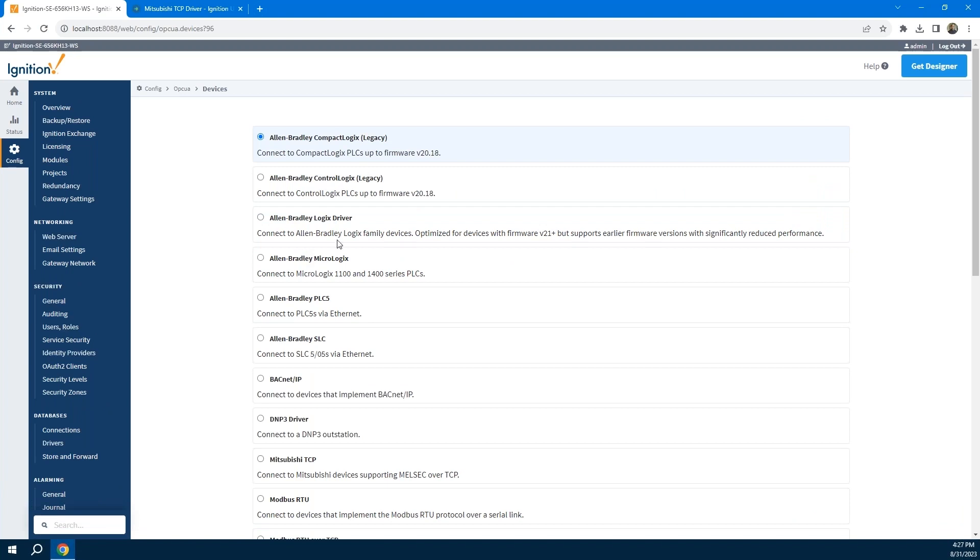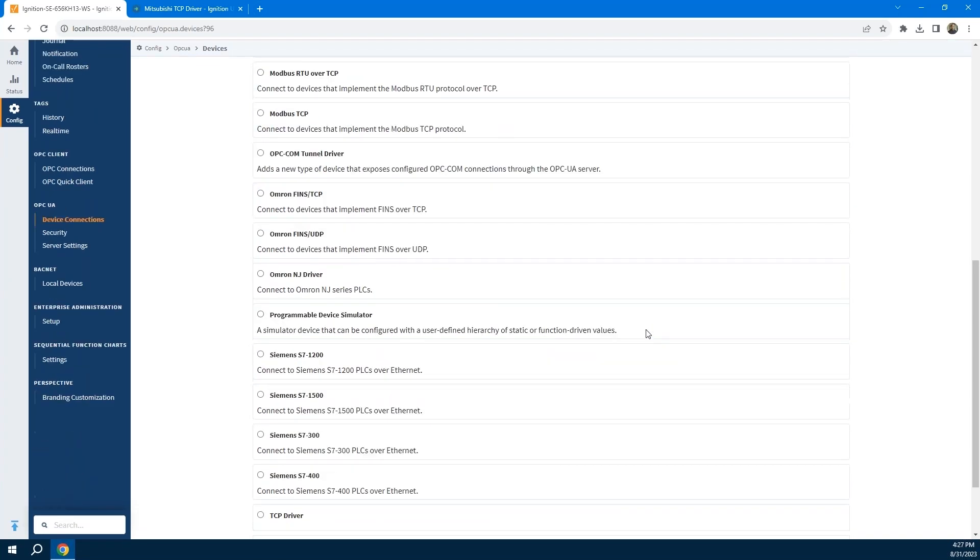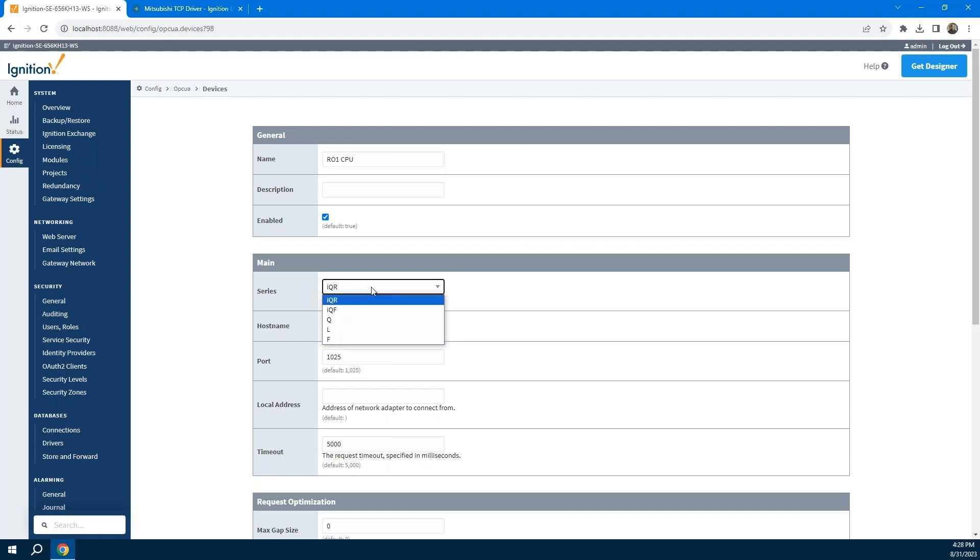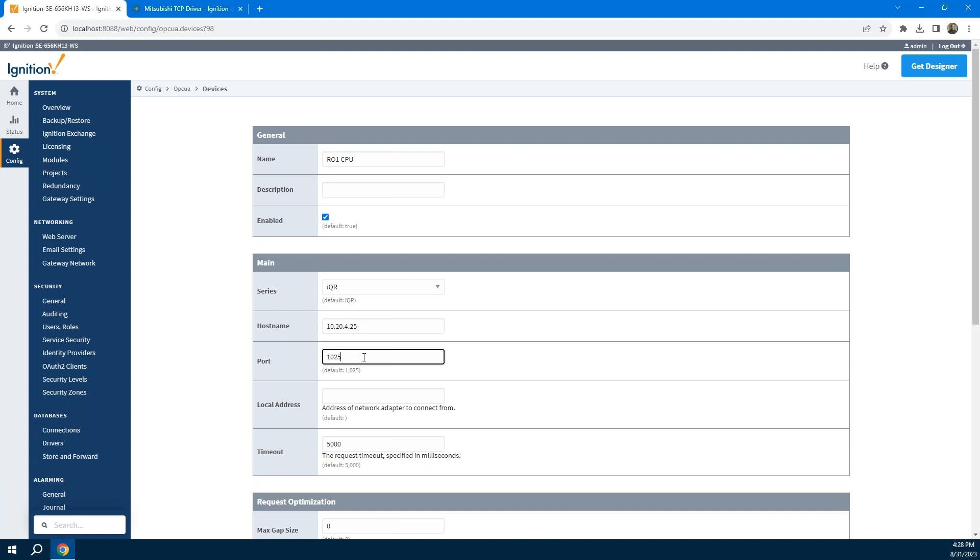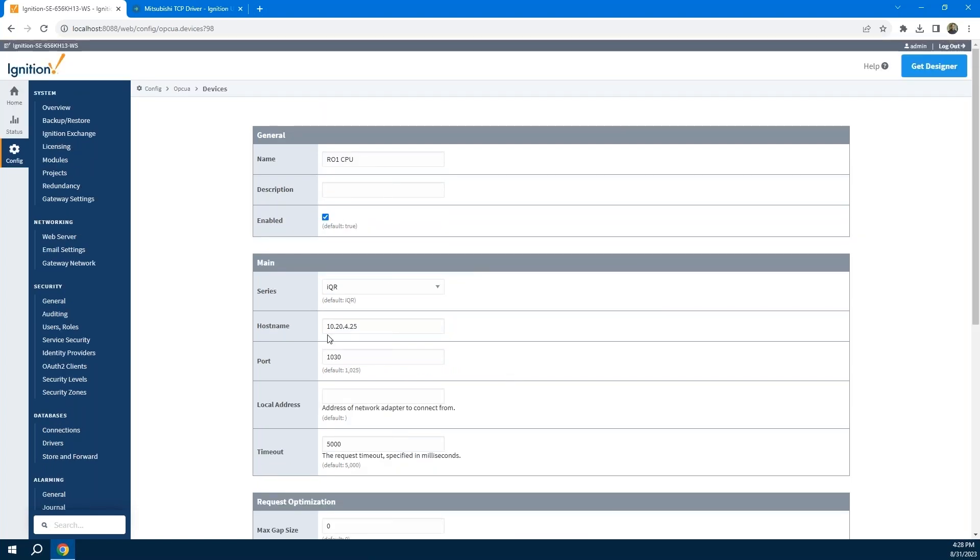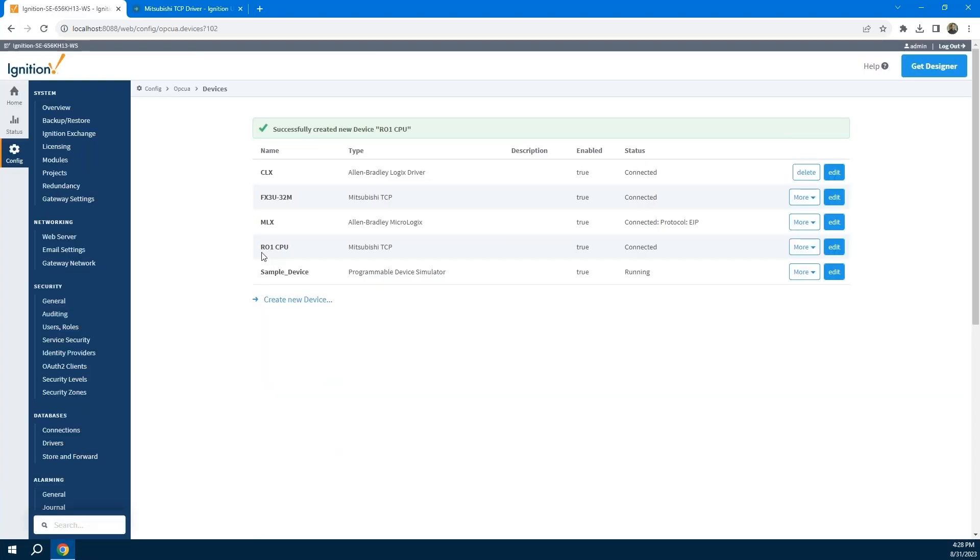Is Mitsubishi our first driver? No, we have many drivers for many different kinds of devices, but today we're going to show you connecting up to a Mitsubishi device. In my case here, I'm going to be connecting up to an R01 CPU. It's going to be an IQR series, but this is where you could choose whichever series of device that you have. I'm going to put in the IP address of my particular device, which is as seen there. For my port, it's not 1025, it's on 1030, so I'm going to change that. All I really needed to do was give it a name, give it a host name or IP address and define the port. I can say connect, and you can see it added this new device connection and our status is connected.